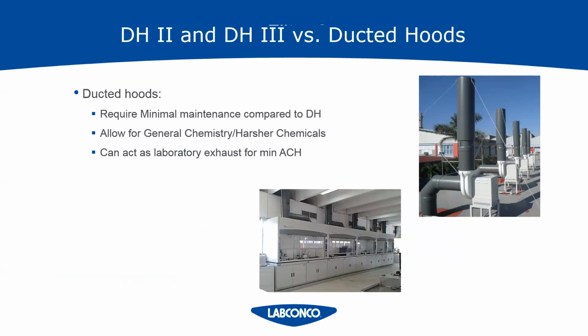So adding a ductless hood is not going to contribute to that air exchange rate, right? Because it's not sending air out. The air changes take into account how much air is supplied to the room and how much air is exhausted from the room. So that exhaust is going to have to come from another source if you don't have any other fume hoods in that room. So there's just general exhaust, and that's probably what would have to be used. So if your intent is to save money, look to see if your minimum air changes are met first, because you may have to exhaust out anyway.